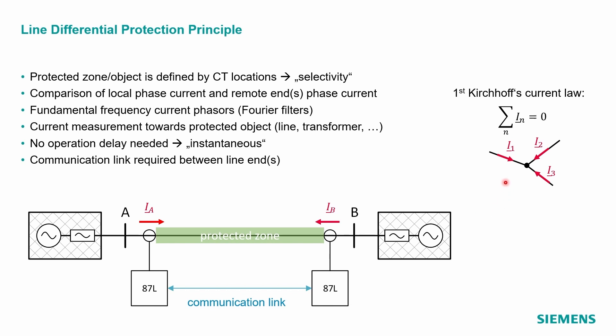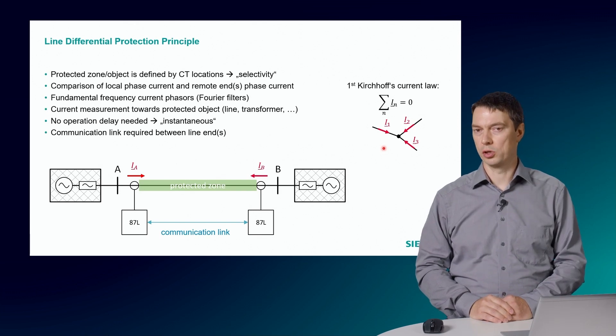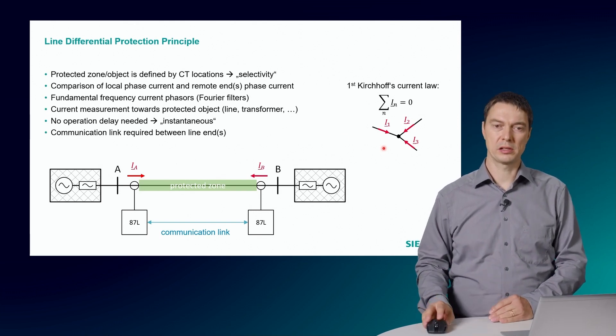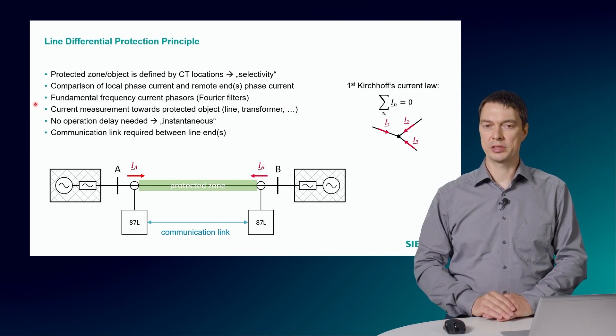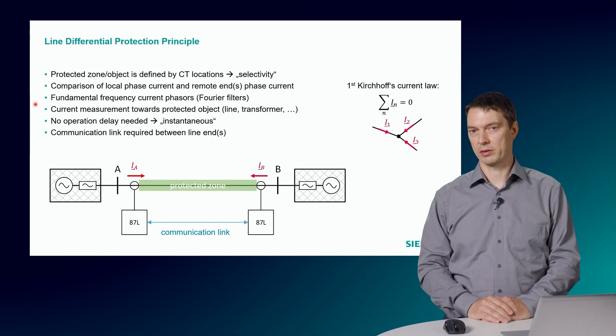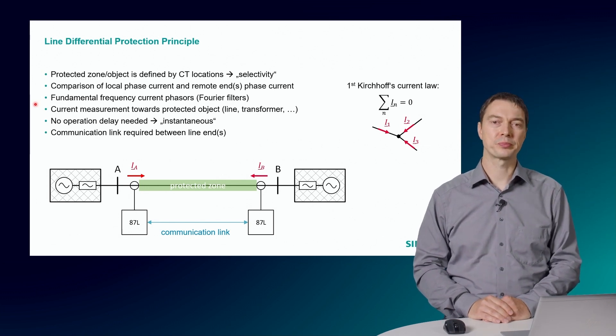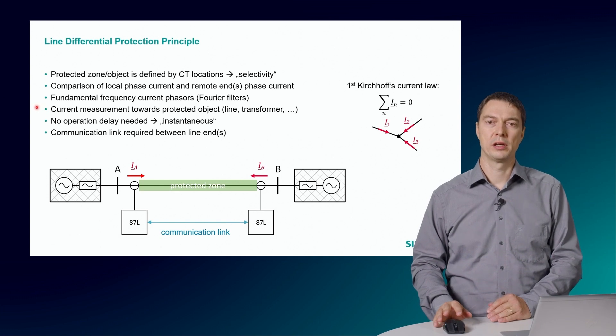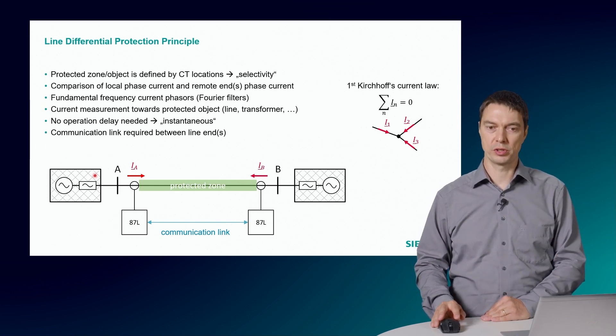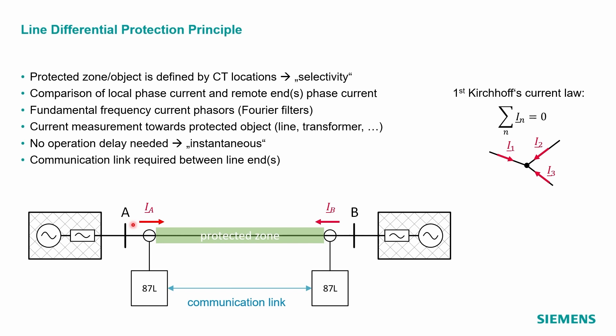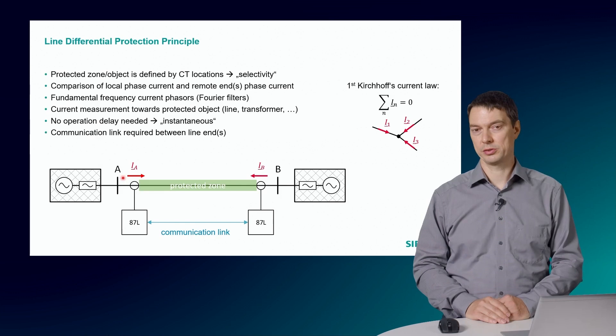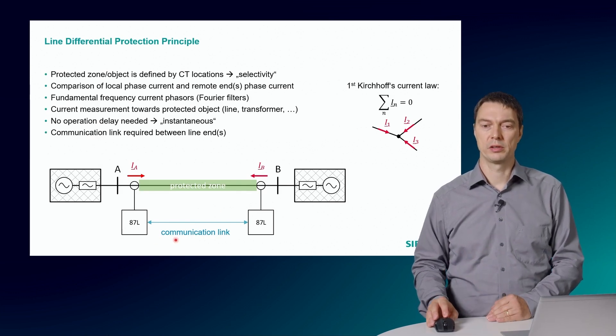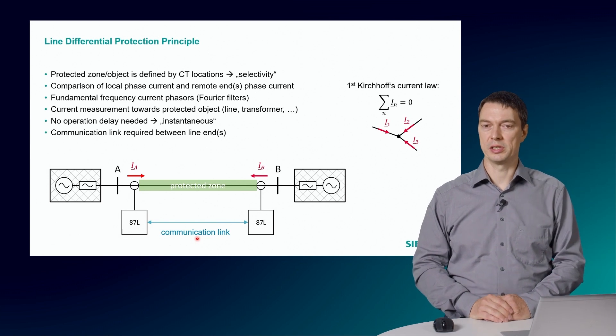And the Line Differential Protection Principle is based on comparison of the local phase and the remote phase currents. It applies the first Kirchhoff's law, which is the current law, which says that the sum which flows into a node always equals to zero. The fundamental frequency component is evaluated, which is obtained using Fourier filters. But there are also other methods on the market. The current measurement is normally defined towards the protected object, which is shown in the figure with the arrows pointing towards the protected object or into the line. There is no need for an operational time delay, so an instantaneous operation is obtained by this protection principle. But you need a communication link between the relays, which I already mentioned, which needs to be secure and safe.